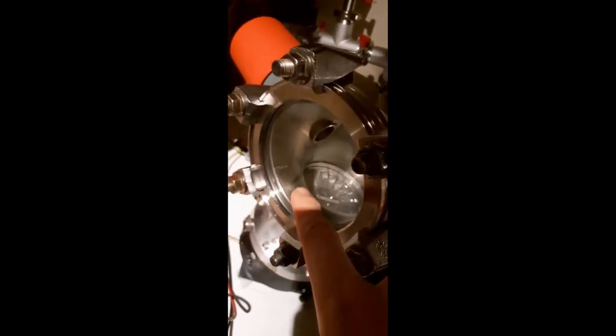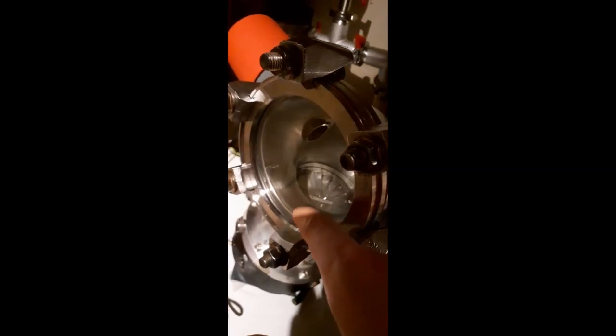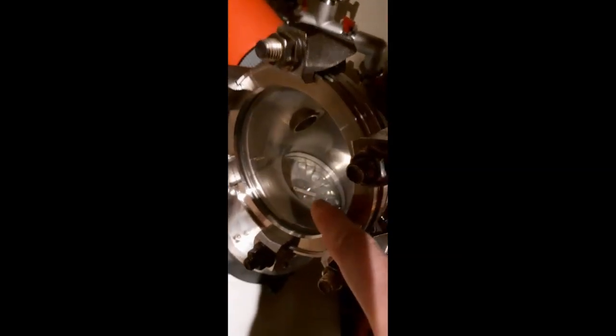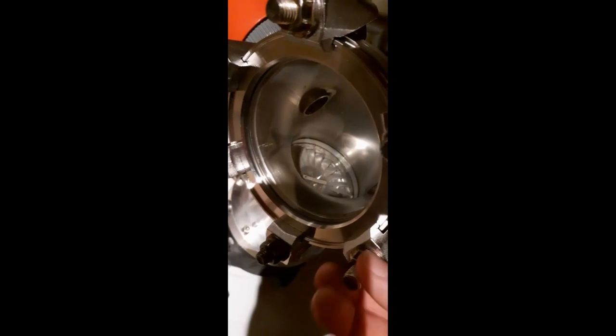If anything at all enters those rotor blades down there, those will be spinning around 80,000 rpm. If anything touches those, the entire pump will just disintegrate. And on this long hose here, it'll just fly around the room like a mace. And that's not a very nice prospect. The pump is bolted down, as you can see here. But yeah, that's pretty much the system.